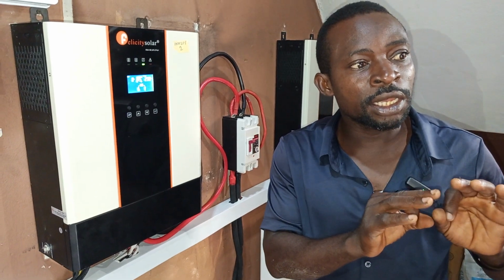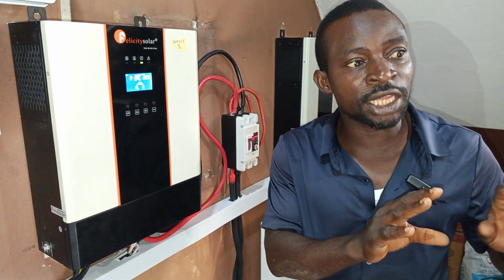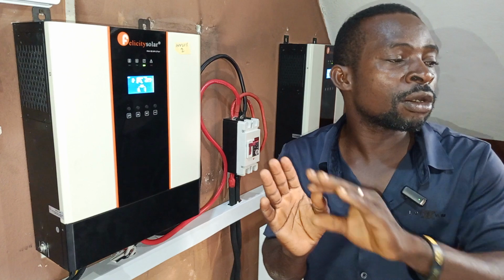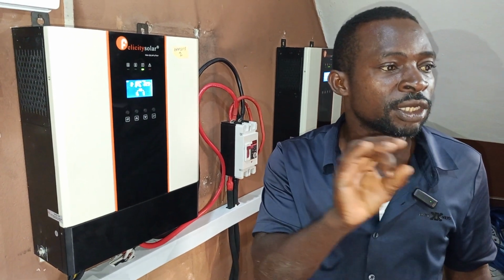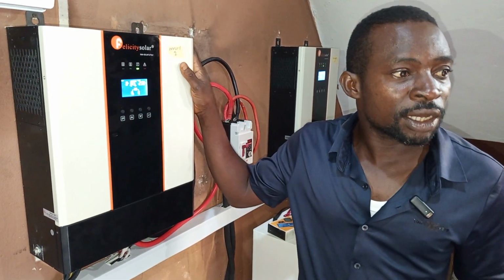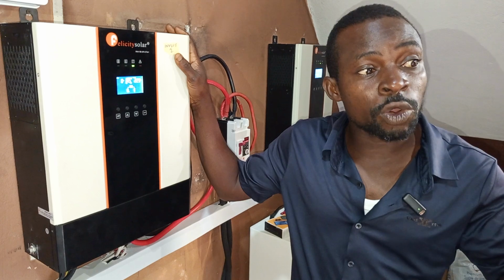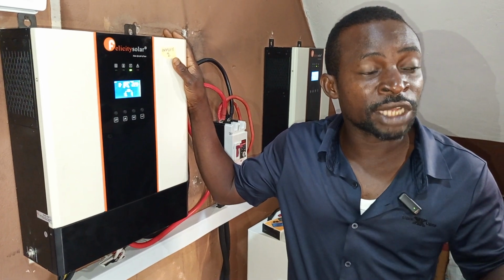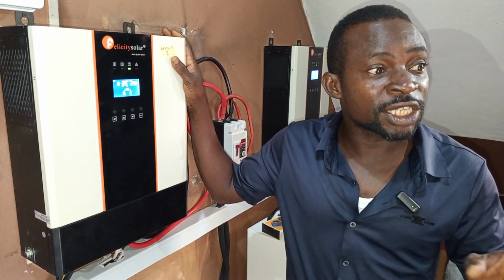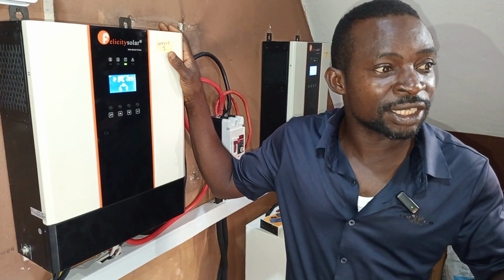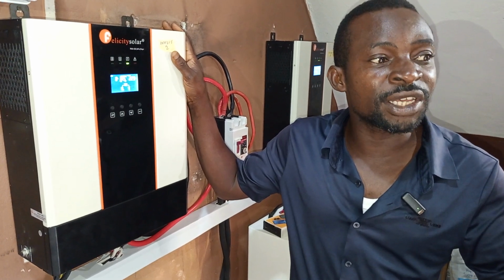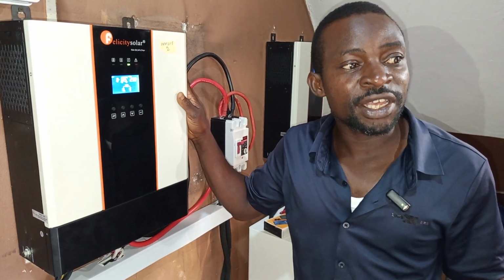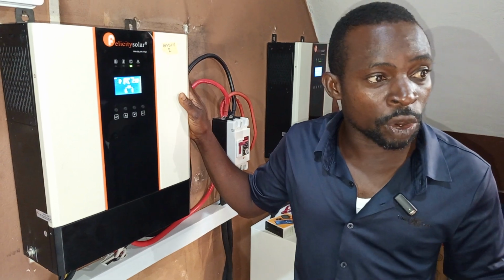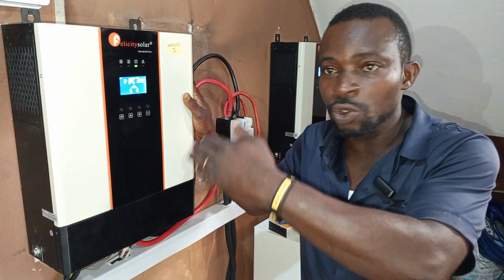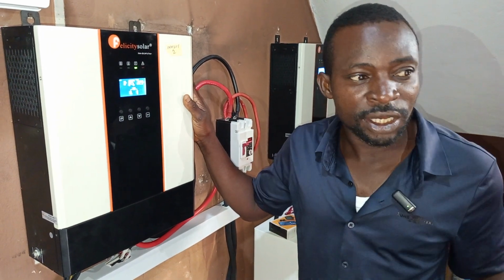If you are buying the transformer-based one, like that 10 kVA with the charge controller, there's what we call power factor, because it's an inductive load with a transformer in it. At 0.8, if you multiply it by 10, it gives you 8 kVA. But this 5 kVA is truly 5 kVA. You can put it on your inverter and see it showing you the load gradually, as we showed you.